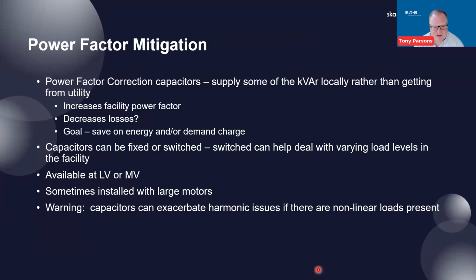The capacitors are typically available either at low voltage or medium voltage. Sometimes they're installed with large motors. Large motors may not have the best power factor, and so in order to keep from correcting when the motor's not on, we switch the capacitor with the motor. Common, at least in some industries.